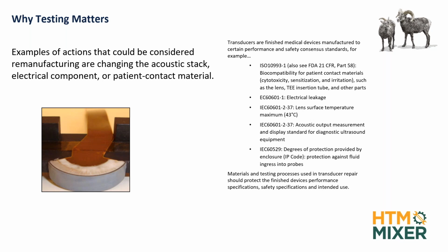So that's 60601-1. And then lens surface temperature, what touches the patient. That lens can never generate heat above 43 degrees C. Has to be in there. It starts to burn the patient. They don't like that. I haven't found one that likes it yet. And then also there's biocompatibility testing that needs to be done, etc.